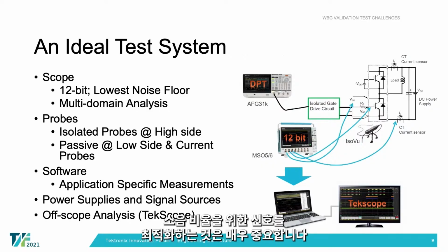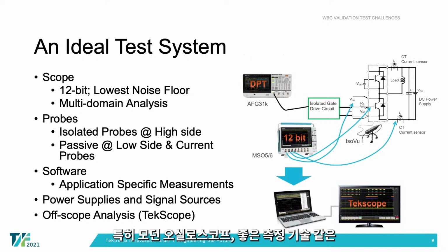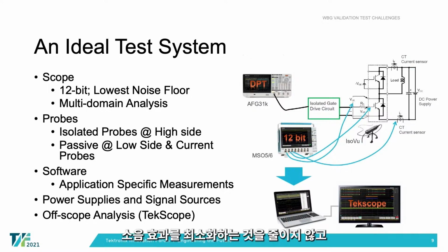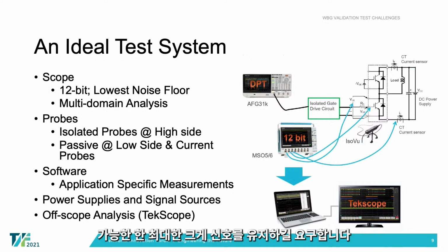It is very important to optimize signal-to-noise ratio. In all measurement systems, especially digital devices such as modern oscilloscopes, good measurement technique requires keeping signals as large as possible without clipping, to minimize the effects of noise and maximize vertical resolution.